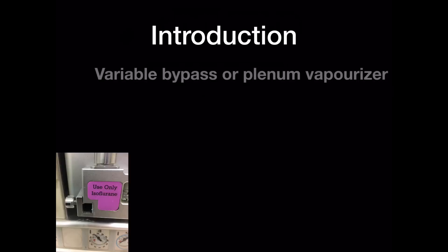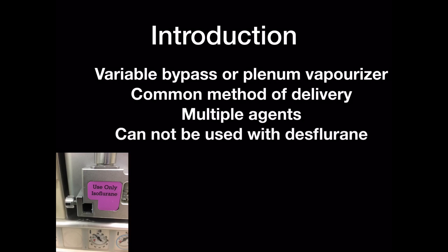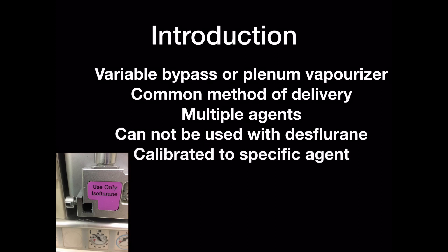A variable bypass or plenum vaporizer is a common method of delivery of volatile anaesthetic agents. It can be used safely with sevoflurane, isoflurane and halothane. It cannot be used with desflurane, and we will cover the reason for this in a subsequent tutorial. Each vaporizer is calibrated to a specific anaesthetic agent and cannot be safely interchanged between agents due to their differing physico-chemical properties.